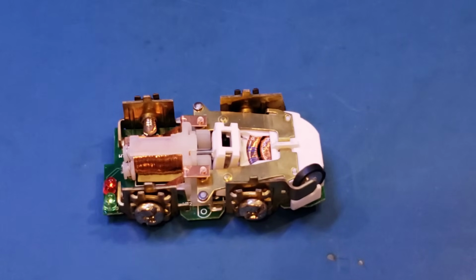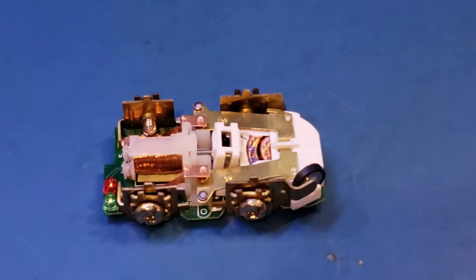Anyway, for this reason, almost all modern GFCI receptacles employ some kind of grounded neutral detection circuitry. And this is why you have a second coil here. You can see we have an inner coil and outer coil, and the outer coil here is for grounded neutral detection. By the way, these two coils don't have to be concentric. And the reason Leviton did this, I assume, is to save space.